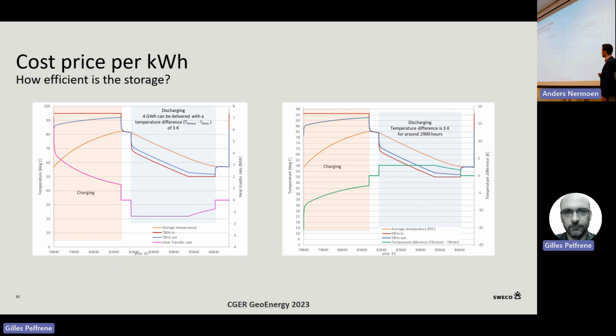This is the delta T between the bore heat exchangers during discharging, and this is the temperature in the storage. One of the things with the bore heat exchanger that can withstand 95 degrees is that it's a certain type of plastic, different from the standard bore heat exchanger, and it has a low thermal conductivity, meaning the heat exchange capacity per meter of well length is a bit less.